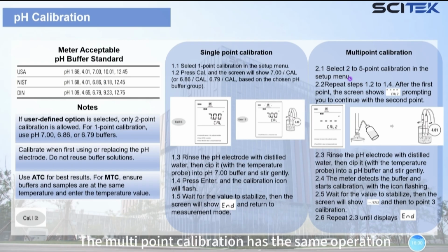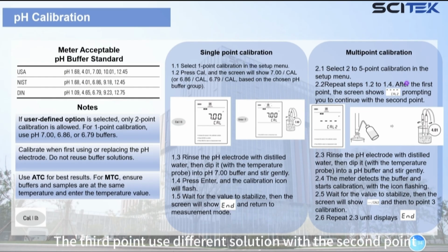The multi-point calibration has the same operation, but when the first point calibration is completed, you should change the standard solution. Usually the first point uses pH 7, and the second point uses 4.01 or 10.01. The third point uses a different solution from the second point. Then you can process the second point calibration, then the third point calibration, until the end icon is displayed on the screen. The multi-point calibration is completed.